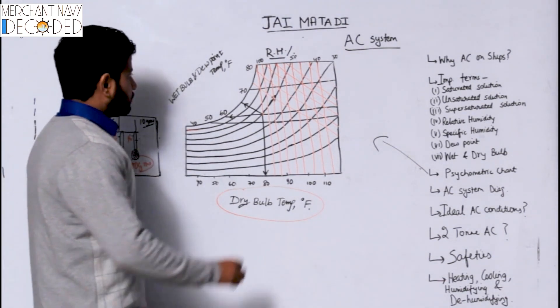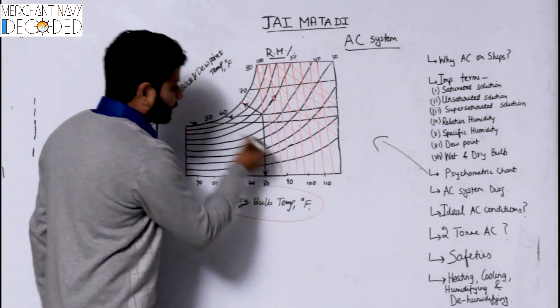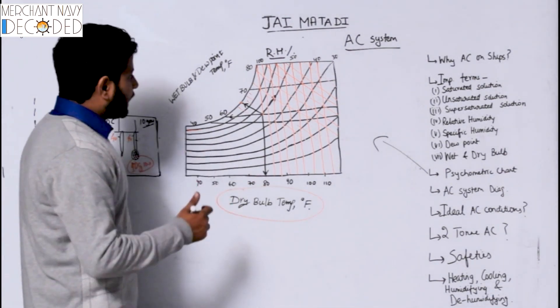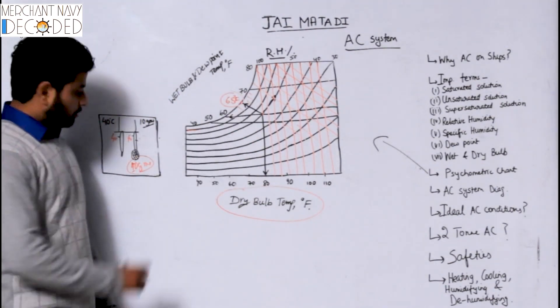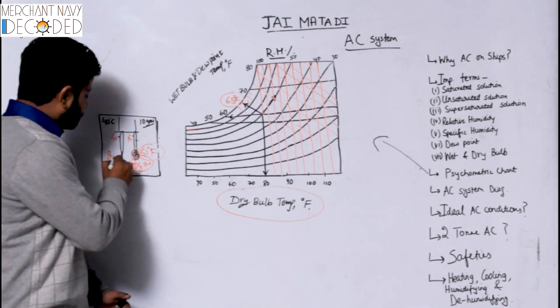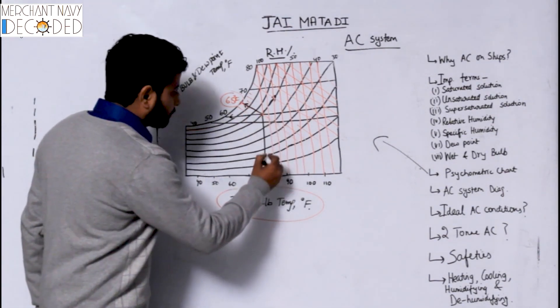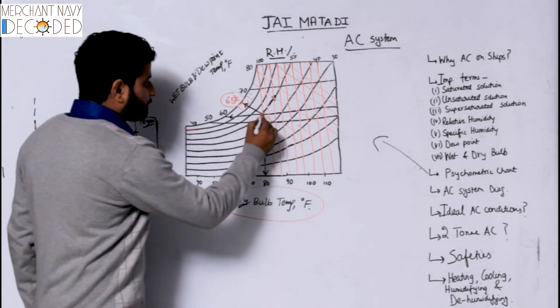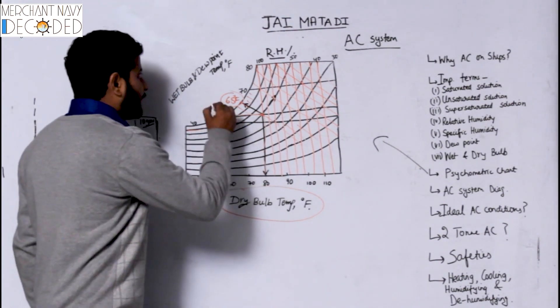Now there are also many diagonal lines on the chart — all these lines are wet bulb lines. Say my wet bulb temperature is 65 degrees Fahrenheit, and my dry bulb shows 80 degrees Fahrenheit. So what I do is I draw a line from the wet bulb value here to here, and a line from the dry bulb value here to here. Wherever they coincide — wherever the straight line meets — that point is at 60 degrees Fahrenheit, and that is my dew point.